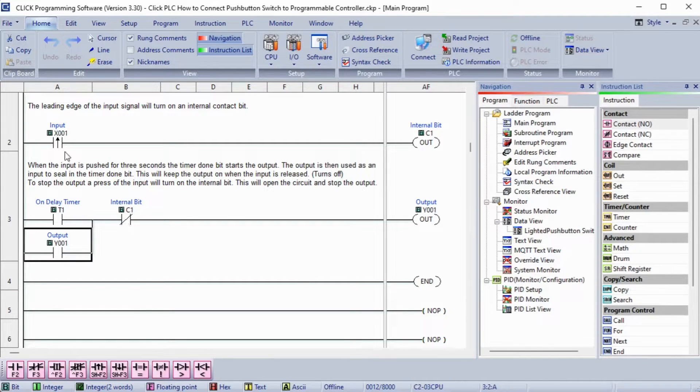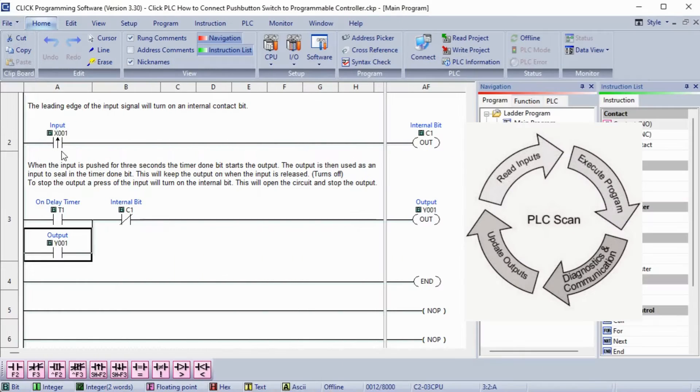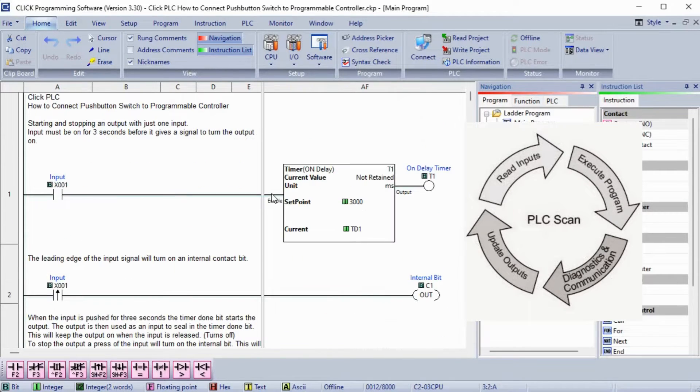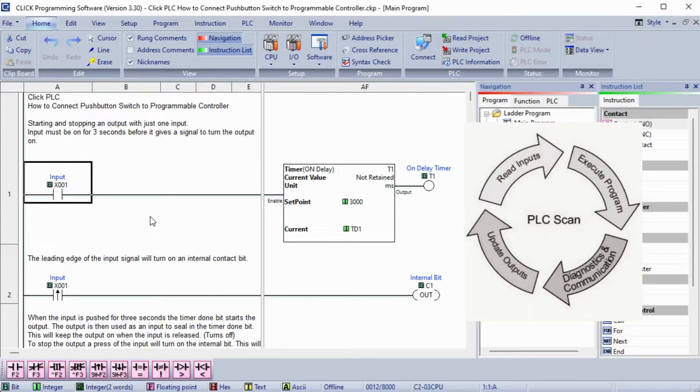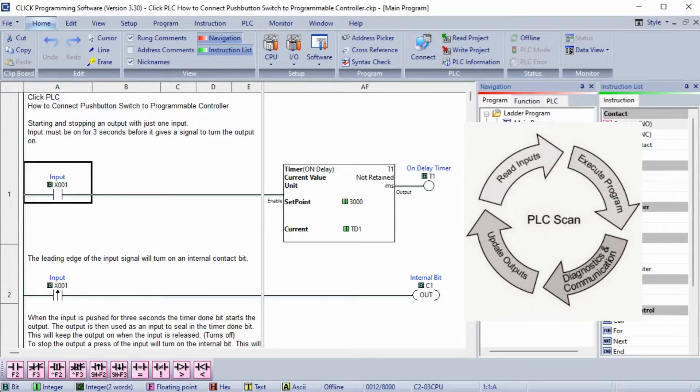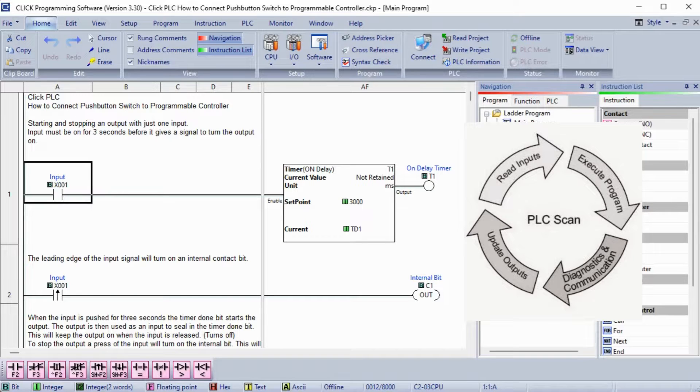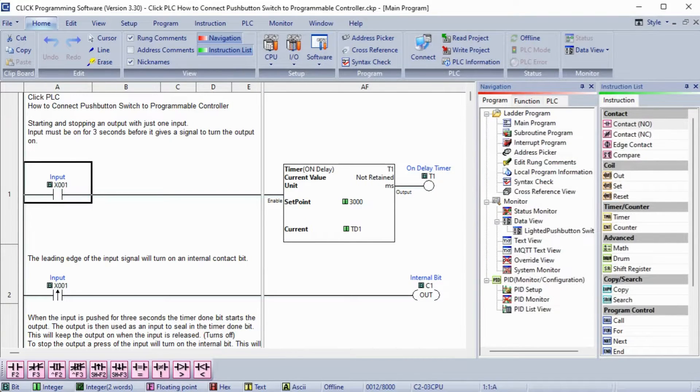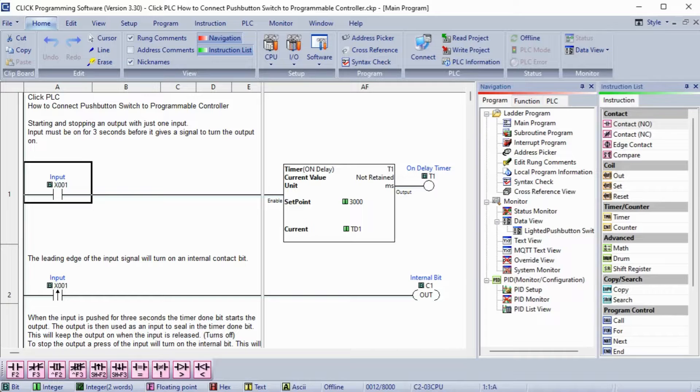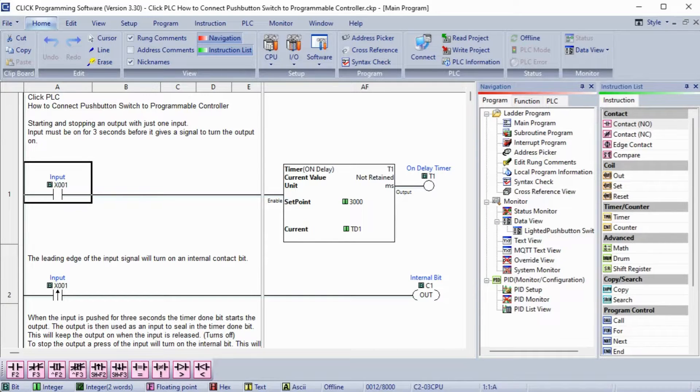Remember that a PLC uses a cyclic scan. This means that the inputs are read, program logic is scanned, and outputs are set many times per second. The PLC solves the program ladder logic from left to right, top to bottom. The conditions from the previous rung are available for the next rung to use.